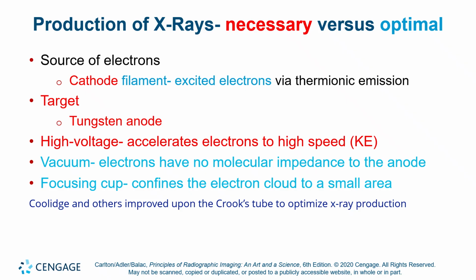Okay, so how do we make X-rays? You might remember from the schematic lecture that we need a source of electrons. That's what the cathode filament and the filament circuit is for, to boil off electrons at the filament via thermionic emission. Thermionic means you create ions by applying heat, and most metals will do this. If you heat them up hot enough, they'll start to glow red. That red glow is electrons getting excited and then relaxing back down. If you keep heating it, the red will turn to orange, then to yellow, then to bright white. And then your filament will melt if you keep pushing it. So we want to stop at bright white, maybe stopping at yellow.